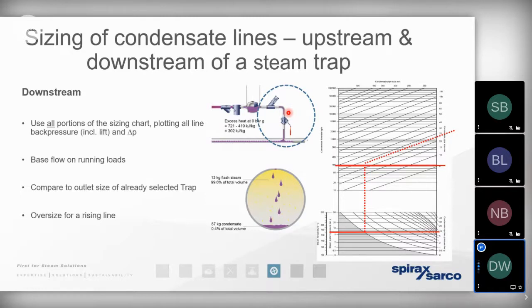So the only way that condensate can give up that sensible heat is by some of that heat energy moving from sensible heat back to latent heat. So a certain mass or a certain percentage of that condensate is going to change state from a liquid back to steam again. We refer to that as flash steam. The problem we have with flash steam is, first and foremost, it's a gas. So it's going to exist at a far, far greater volume than the condensate does as a liquid. What you may recall from previous presentations is that a kilogram of condensate has a volume of 0.001 cubic meters when it exists at zero bar gauge. But a kilogram of steam at the same pressure is going to exist at a volume about 1,673 times greater. So, of course, we've got to size the downstream pipework to allow for that huge increase in volume.